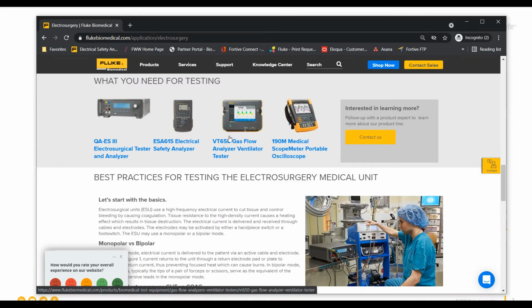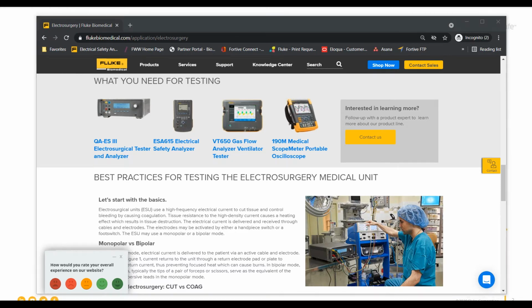So some things you might want to consider. Not only do you need your QA-ES III Electrosurgical Analyzer, you might also need your electrical safety analyzer. Remember, once we're done, we're going to do our output tests, our CQM tests, or contact quality monitor testing. We're going to do our bipolar, our LigaSure, high voltage testing, or high frequency leakage testing, our cross coupling testing. All that can be done with the ESU analyzer, but then we need to do the rest of our electrical safety tests. So you need an ESA.